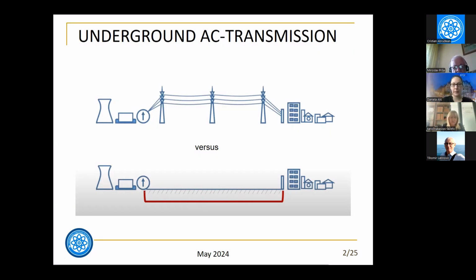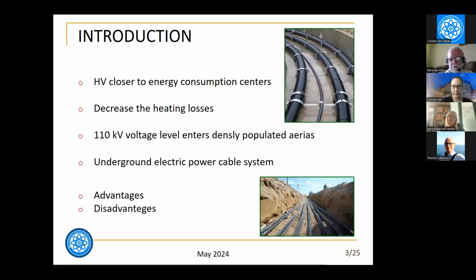Increased city area with increased power consumption inside it now demands a different approach. Due to higher current inside the distribution systems, the heating losses became very high, and the conductors frequently express an overload state. For this reason, around the world there is an intention to drive the high voltage system into the city area closer to the consumers. Naturally, this goal could not be achieved with overhead systems, and the cable system must be involved.